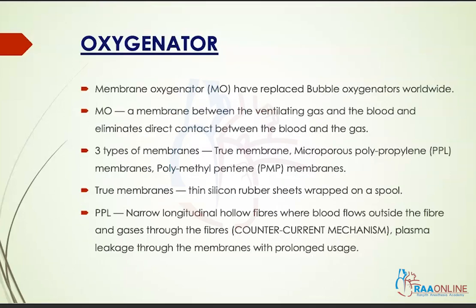Coming on to the first component, which is the oxygenator — worldwide, membrane oxygenators have replaced bubble oxygenators, so bubble oxygenators are not seen in most places, at least in developed countries. A membrane oxygenator consists of a membrane which separates the ventilating gas from the blood, thereby eliminating any direct contact between the blood and the gas interface. There are three types of membranes used: the true membrane, the microporous polypropylene membranes, and the polymethylpentene membranes.